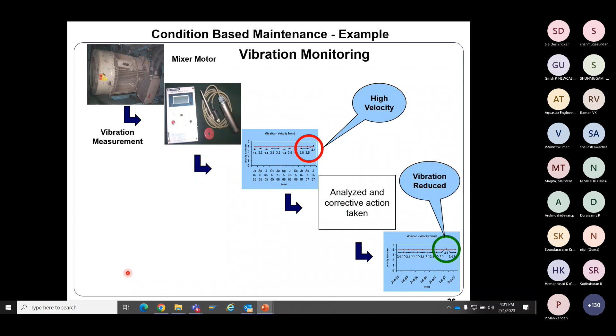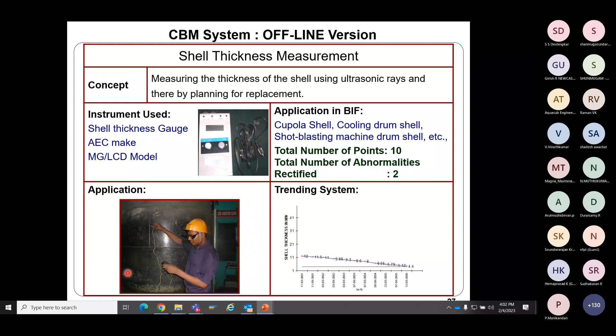Shell thickness measurement: wherever equipment shells need measuring, a minimum thickness has to be maintained, for which you can use appropriate methodology. UT can be used, and trending can be done, based on which time-based replacement can be evolved. These are the conditions by which I can sign off saying this can last for the next year until the next CBM.